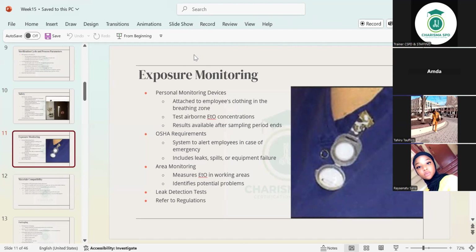It's attached to employees' clothing in the breathing zone, which is anywhere within the reach of your breath, like your nose, mouth. It should be around here. So you see where this one is hanging, right on the chest, like that. So it's supposed to take a sample of whatever air you're breathing in at that point. All right. And then the test of airborne ETO concentration. That is what this thing is supposed to do. By taking the sample, they could test the airborne ETO concentrations to see what level is in the room. If it goes beyond the accepted level, they will have to either turn the machine off or call the specialist and the engineers to come and look at it.